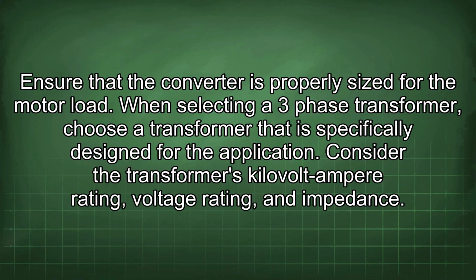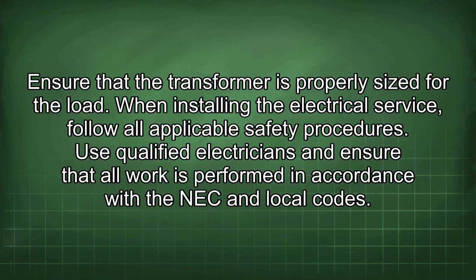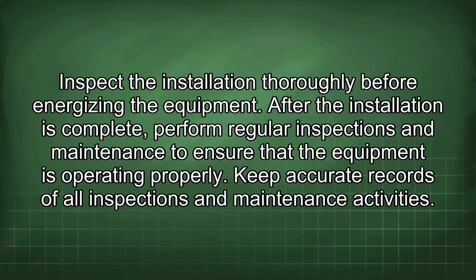When selecting a 3-phase transformer, choose a transformer that is specifically designed for the application. Consider the transformer's kilovolt ampere rating, voltage rating, and impedance. Ensure that the transformer is properly sized for the load. When installing the electrical service, follow all applicable safety procedures. Use qualified electricians and ensure that all work is performed in accordance with the NEC and local codes. Inspect the installation thoroughly before energizing the equipment. After the installation is complete, perform regular inspections and maintenance to ensure that the equipment is operating properly. Keep accurate records of all inspections and maintenance activities.